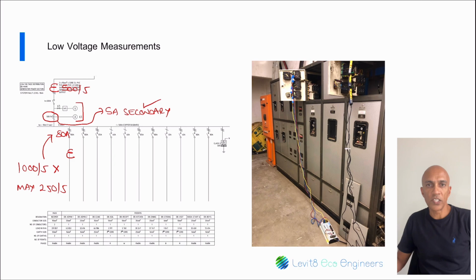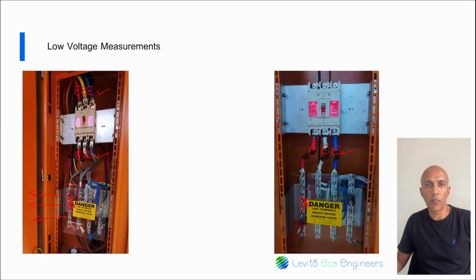The voltage connection is quite simple, and you could connect to the main bus bar or at the top or bottom of any circuit breaker. Just ensure that if you connect to the load side of any circuit breaker, that the breaker is not likely to be switched off. Otherwise, you will not get any voltage readings.